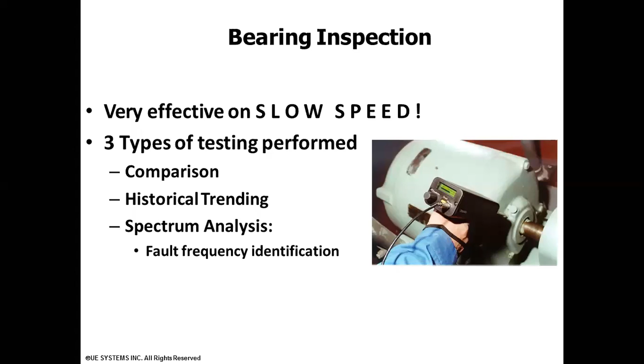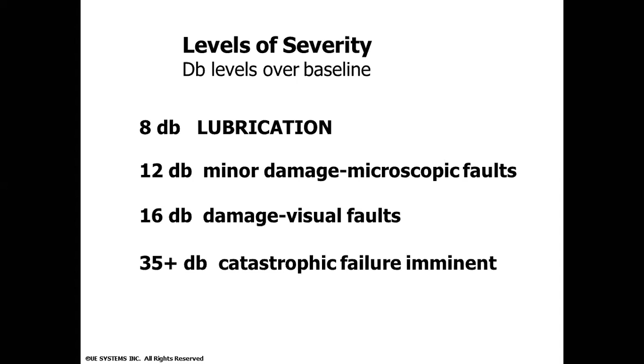Then the level of severity. There are different levels based on your decibel sound. If the sound is 8 decibel, it is because of lubrication. Then at 12 decibel, there is minor damage or microscopic faults. Then if the level increases up to 16 decibel, there will be damage or visual faults. And after 35 plus decibel, catastrophic failure is imminent, and it can be detected.